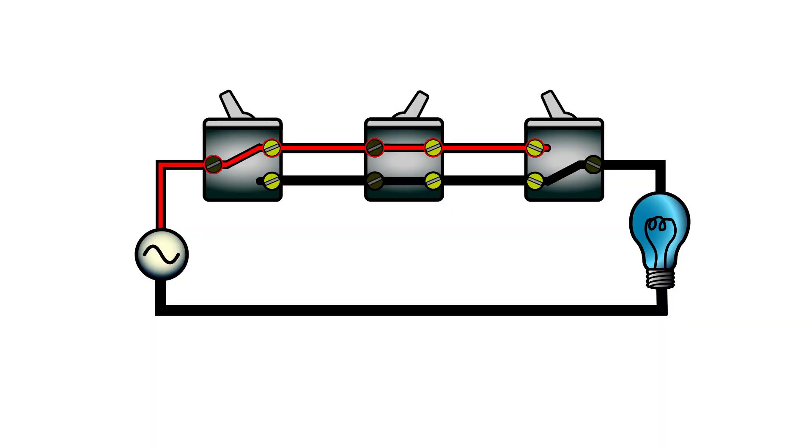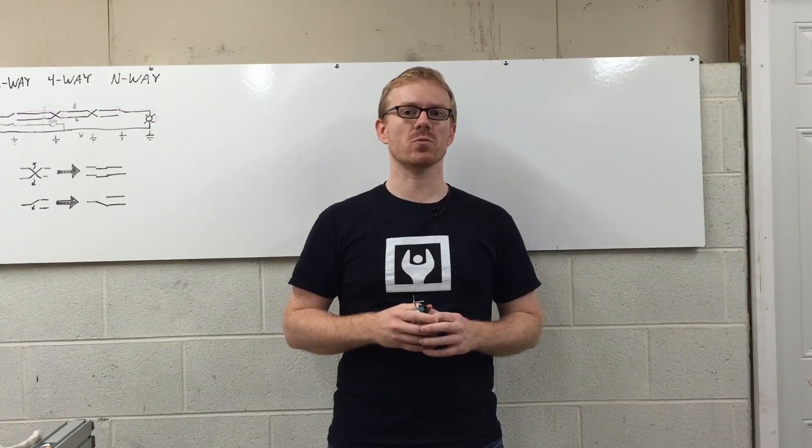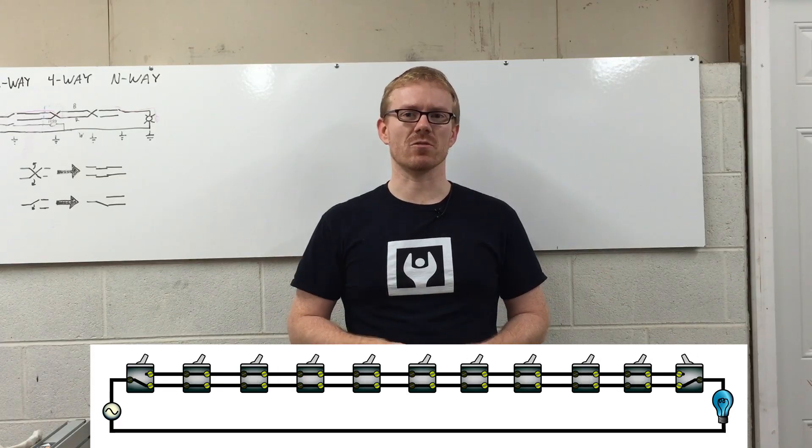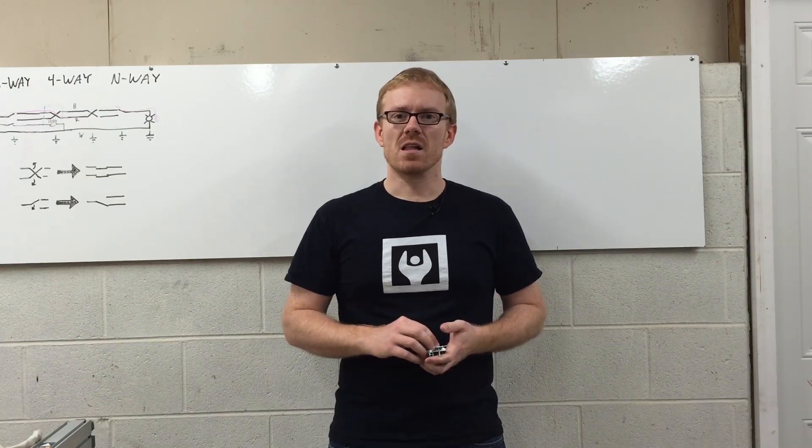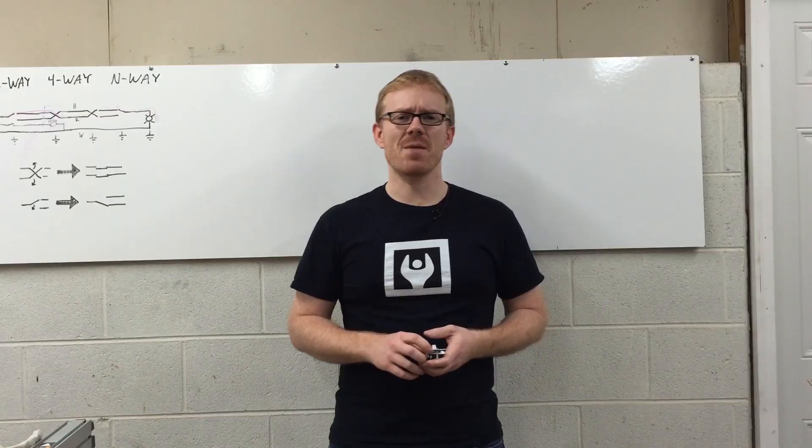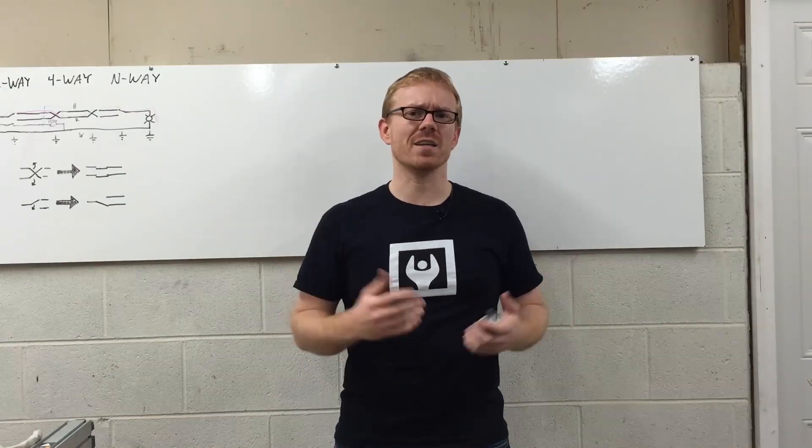Because at all times, one of the traveling pairs is energized, changing the state of any switch in the circuit changes the state of the load. It's possible to add as many four-way switches to a multi-way circuit as you wish. However, it doesn't scale well if you have lots of switch locations, or if you want to do something fancy, like switching based on a timer, a motion detector, or some other concept.